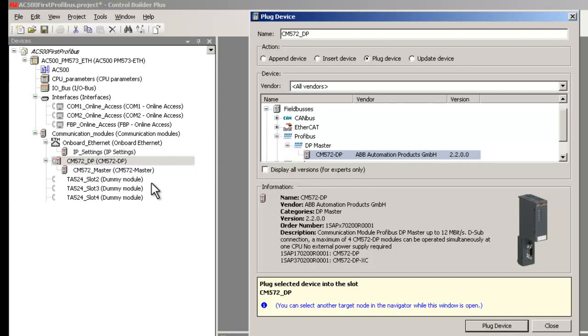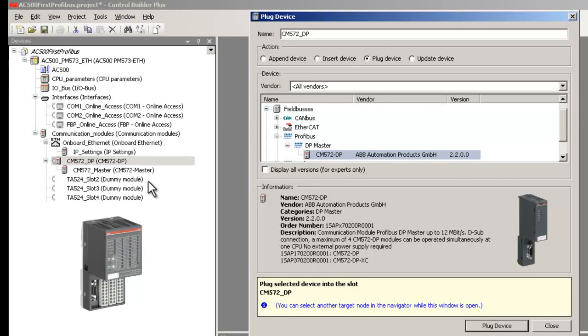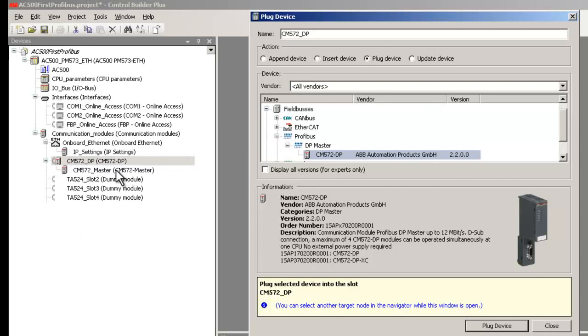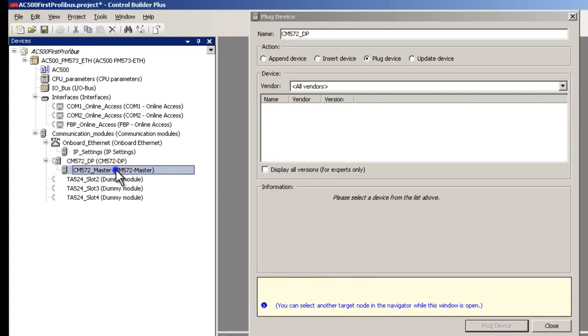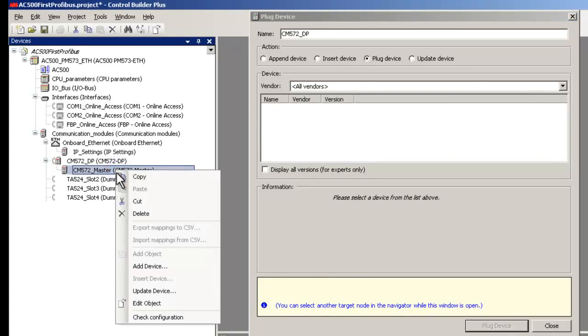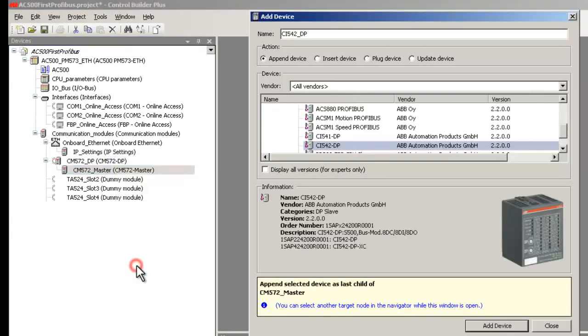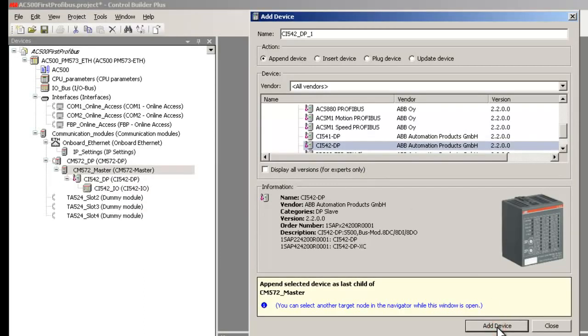Now let's see the configuration steps to include a slave station in this project. We intend to connect a remote I/O station with analog and digital input modules using DP slave bus module CI542DP. Right-click the mouse on the CM572 master and choose the option Add Device. Highlight CI542DP and press the Add Device button. With the integration of necessary GSD file, all other DP slaves that are by default not available in Control Builder could be configured. This is true even for third-party I/O stations and drives integration.